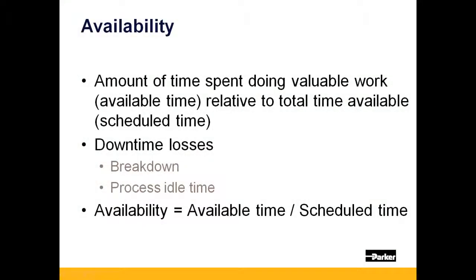Availability is the ratio between the theoretical available time relative to the scheduled time to operate, often called uptime. A reduction in available time indicates a downtime loss. Downtime losses can be attributed to the result of a breakdown, or can come from process idle time while an operator waits for parts or takes longer than normal to set up the machine.